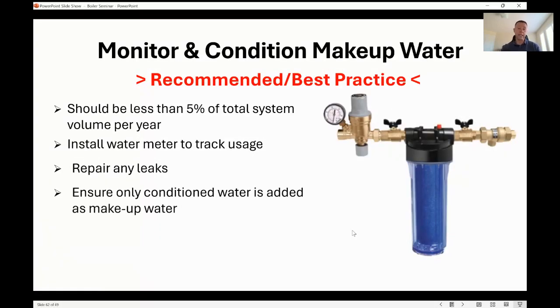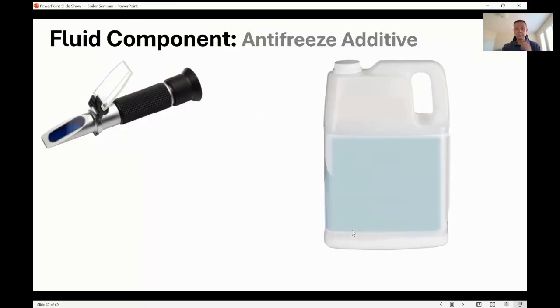I recommend only conditioned water is added. So put something in to condition it, or have one of those tanks, basically a glycol feed tank or whatever, with water. So if it drains, it'll sound an alarm. It'll let you know you've got a leak somewhere in your system.